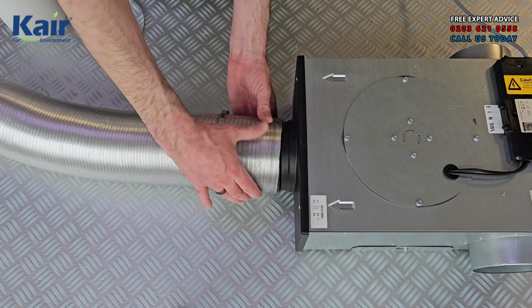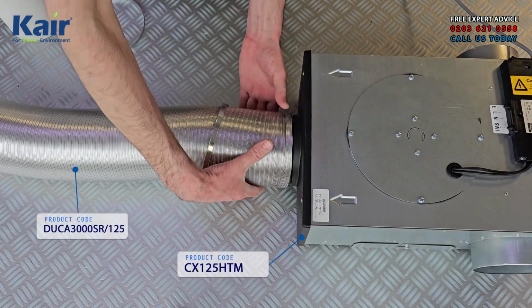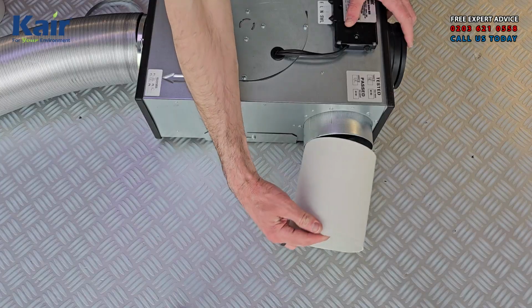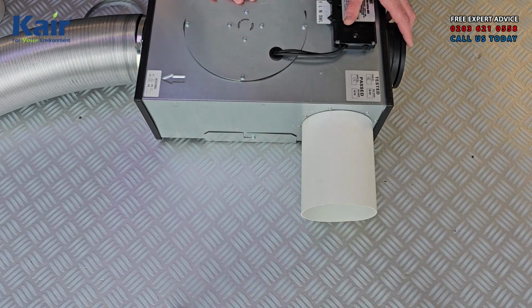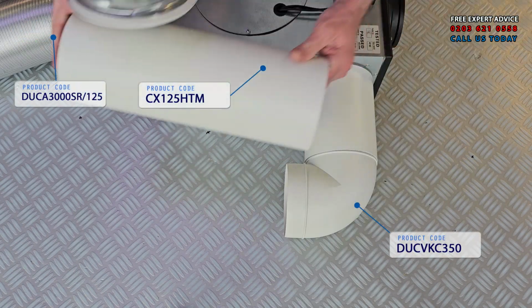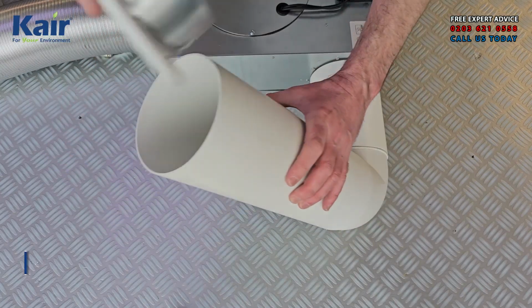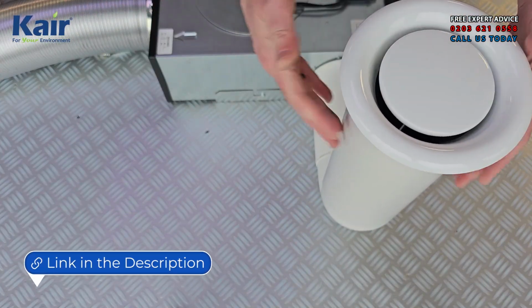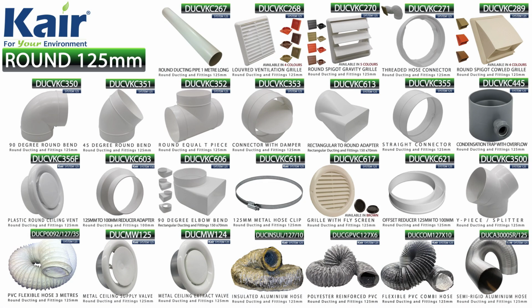As with any ventilation system, the most important thing to check is the spigot size on the fan or unit. If the spigot is 125mm, the system is designed for 125mm round ducting. For medium airflow ventilation systems, a common duct size used is the 125mm ducting system.